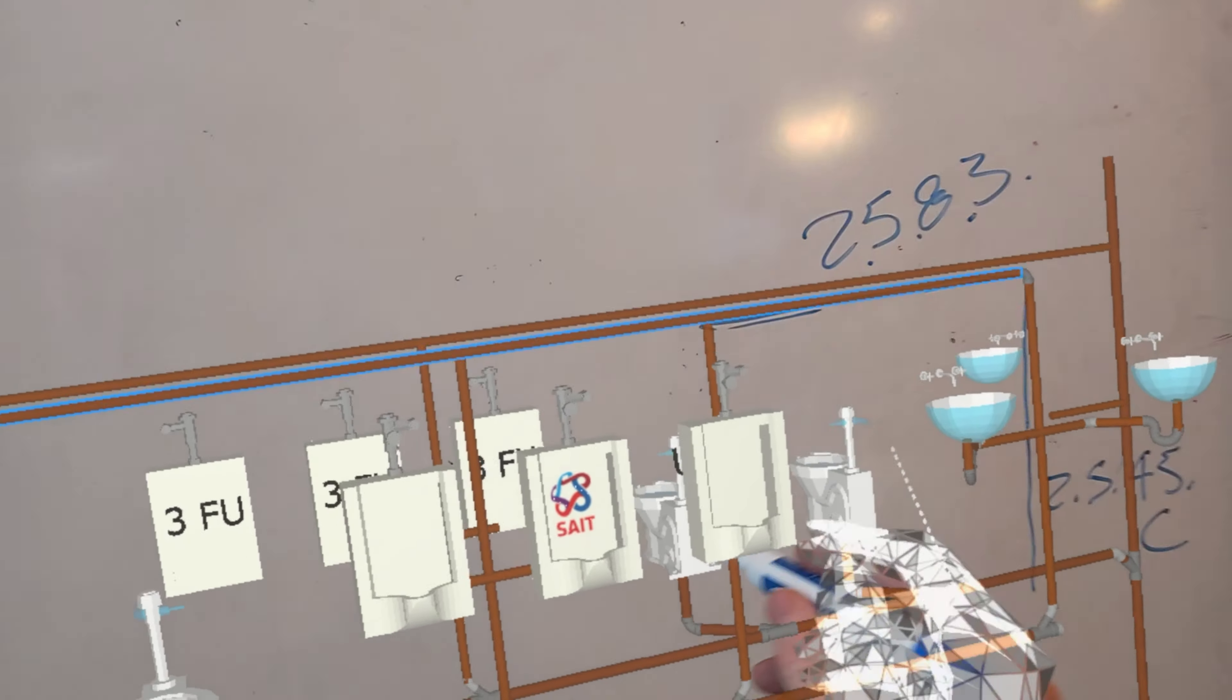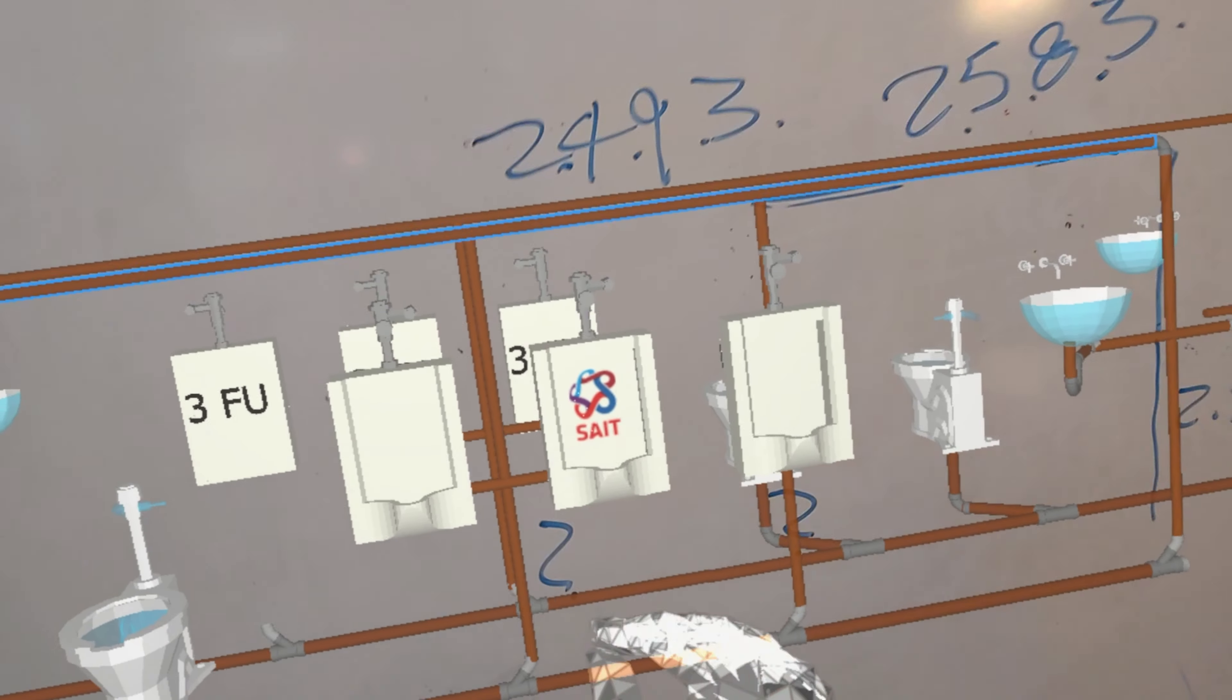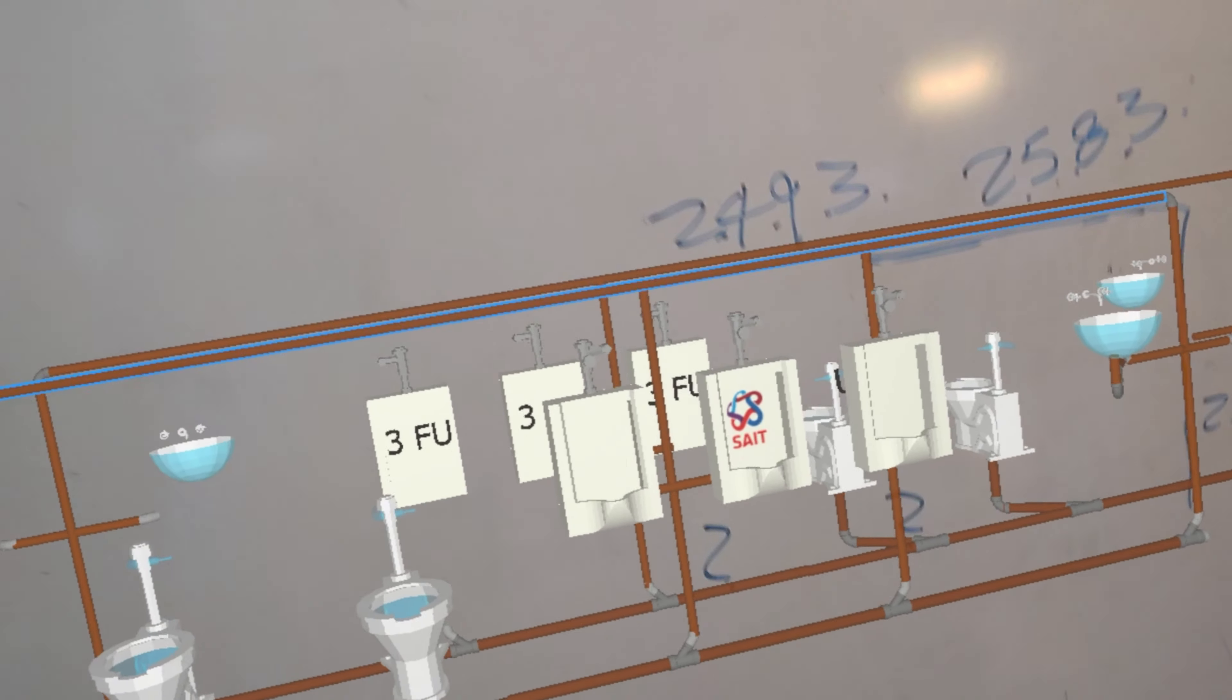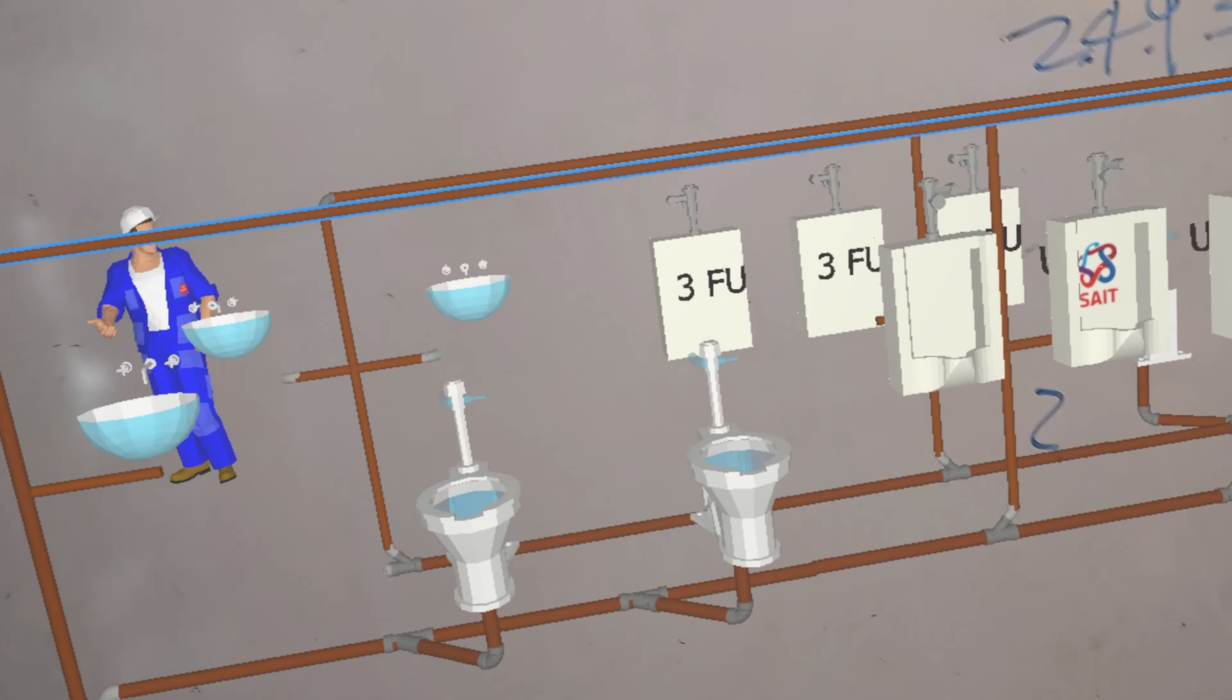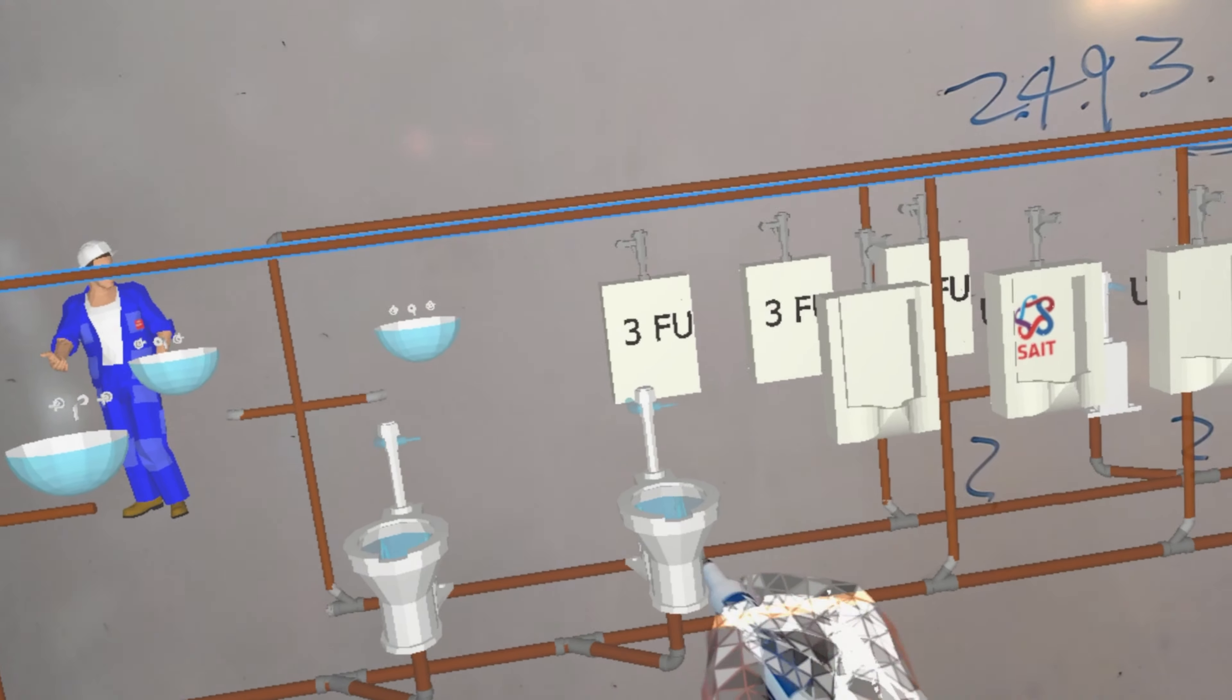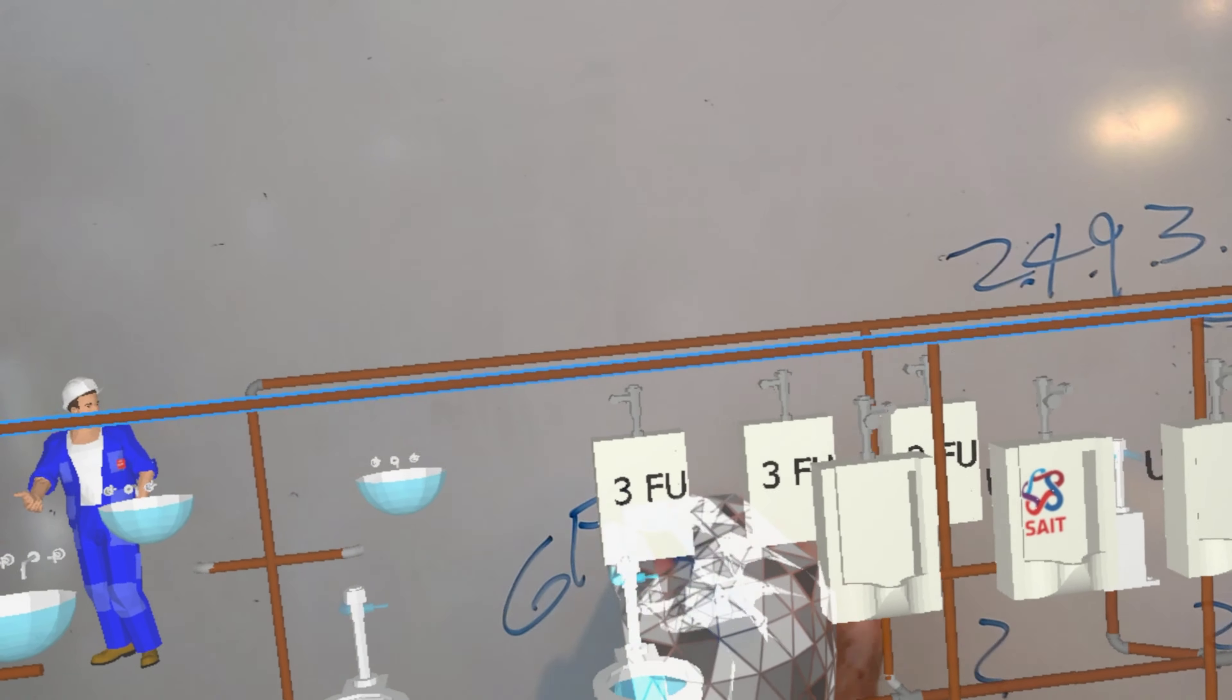And then of course you'd have to figure out the sizes of these two branches. Or this is a branch and this is a fixture drain. So we want to know what they are too in the circuit vent and branch. And then of course at the end we have two flushometer toilets. How many fixture units is a flushometer toilet worth? Well we know they are worth six FUs.